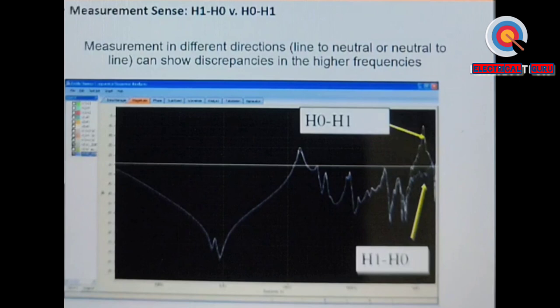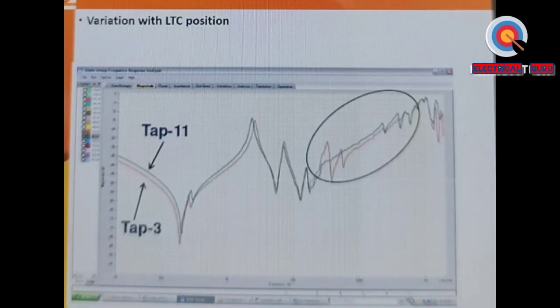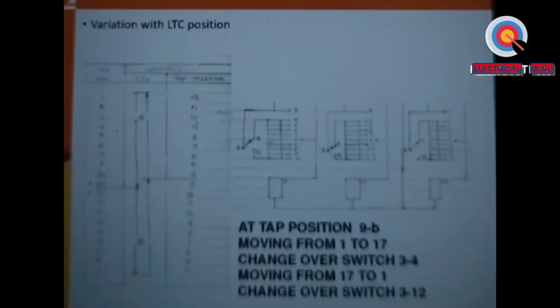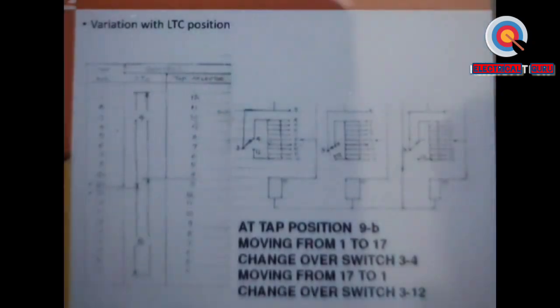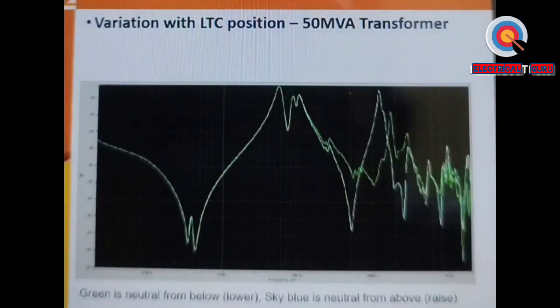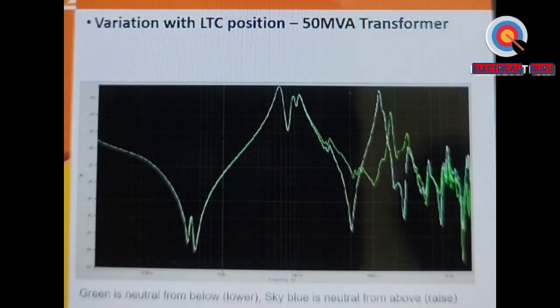Now, as I told you, this test is all about RLC. So if the tap or the tap direction changes, tap 3 and tap 11 physically should be the same, but then the winding is in the reverse direction. So that is where you see it is parallelly shifted. The red line and blue line are displaced by a few dBs, but that is only because of the change in direction, so the inductance and capacitance values change. This is if you have the changeover switch and you don't note it, then this can happen. You can see the distortion is mainly from 10 kilohertz up to 1.5 to 2 megahertz because of the reversal of directions.